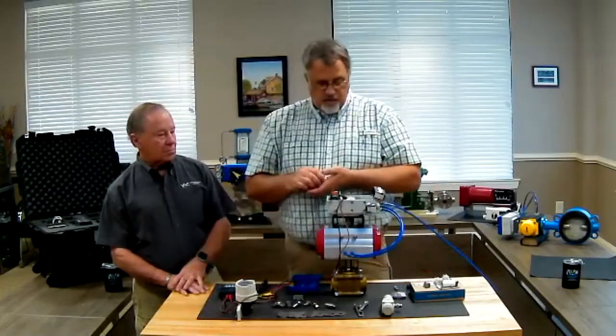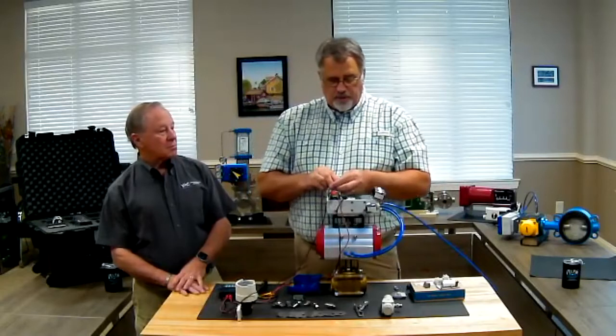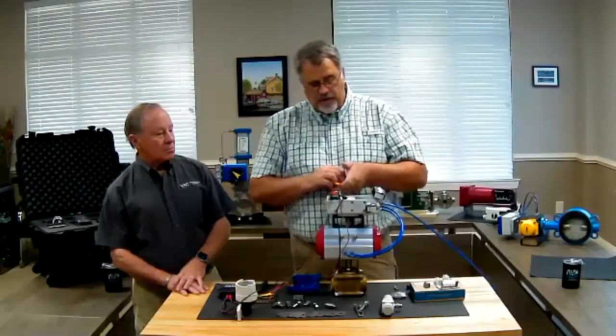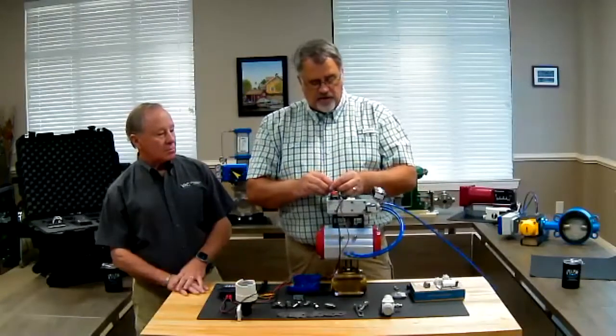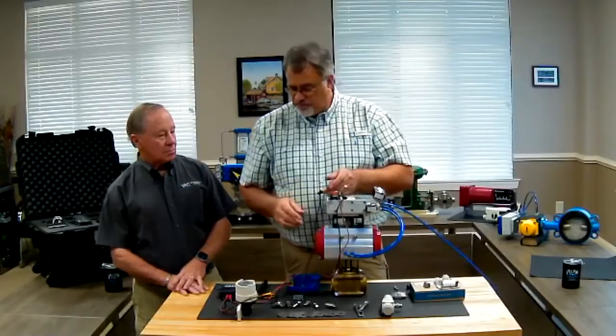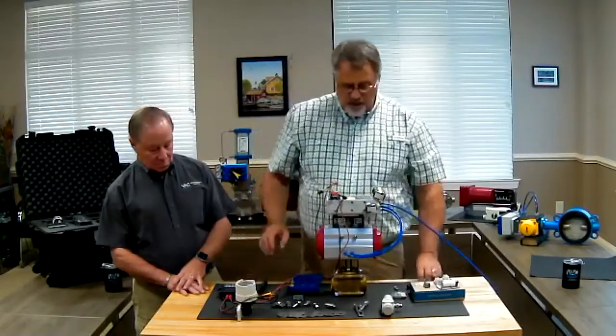Using this loop calibrator, I can actually both drive the positioner and read my feedback simultaneously on the same screen. So I'm going to do a quick calibration here.